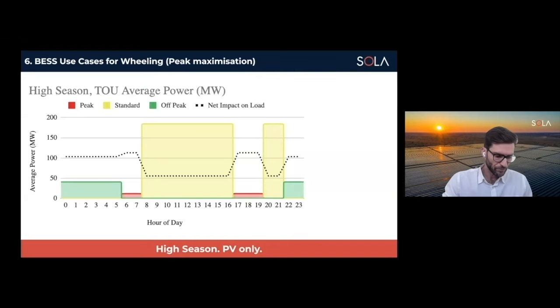In the first case, if you think about an arbitrage model, we take as much solar generated during the daytime as we can, and we soak that down into the battery, and then we dispatch it in the morning and or evening peak periods, which are the times of day when our mining clients typically pay the most for their energy. Those are the peak demand periods. There's a big premium on the power in those times, so we want to shift as much power as possible to those periods.